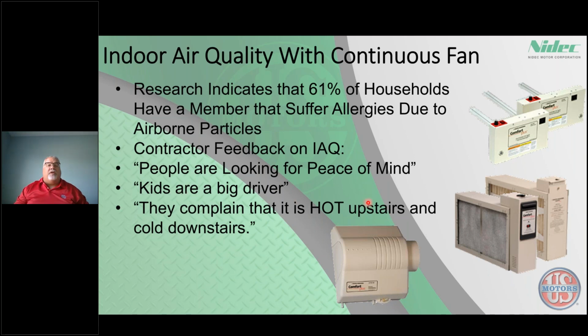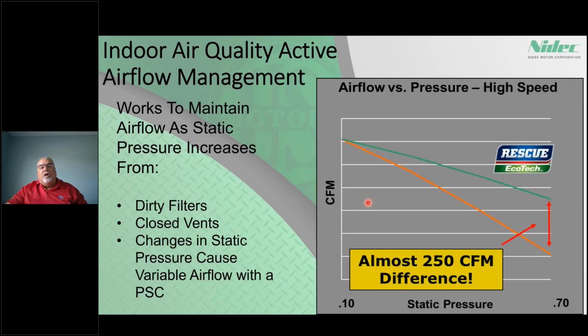You can see some of the other reasons people want indoor air quality with continuous fan. One last thing we talked about earlier: as static pressure increases, we measured this product versus a PSC. The red line is your PSC product and the green line is your EcoTech. At 0.7 static, we were achieving 250 more CFM over a PSC. So this motor does a better job as static pressure increases, keeping the airflow going. This reiterates that a constant torque motor can keep up, but it just can't do as good a job as a constant CFM motor because of its programming.